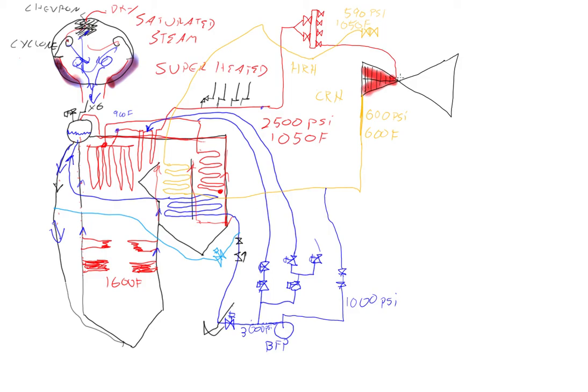If all your steam goes through the high pressure turbine, that's where you actually get the most work. See how you dropped from 2,500 pounds down to 600 pounds? So the rest of the section you're only going from 600 pounds down to vacuum. The majority of your energy was already given up here. So we want as much steam flow to go through here as possible, and putting steam in further down that'll skip that is wasteful.